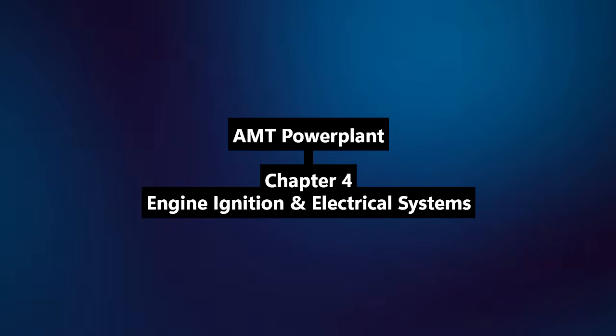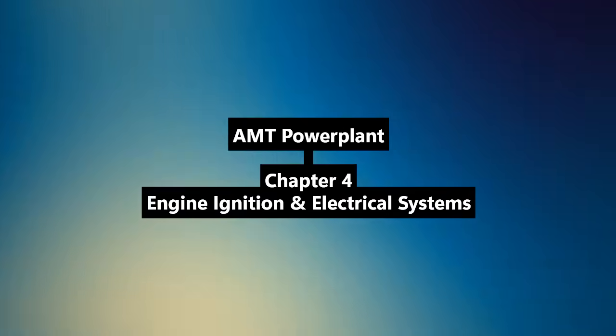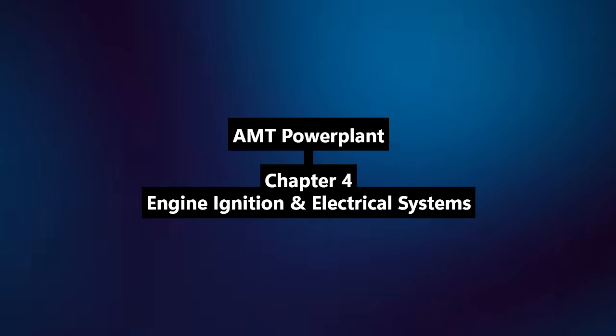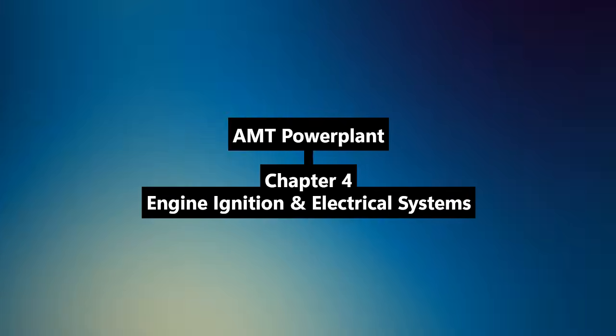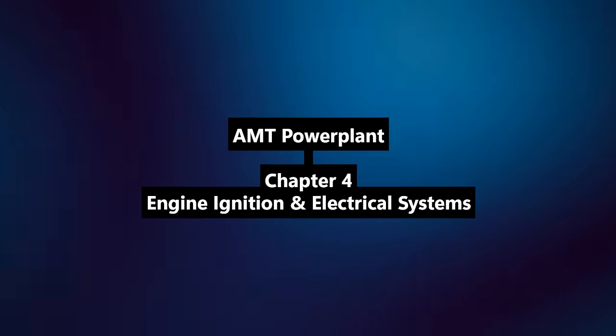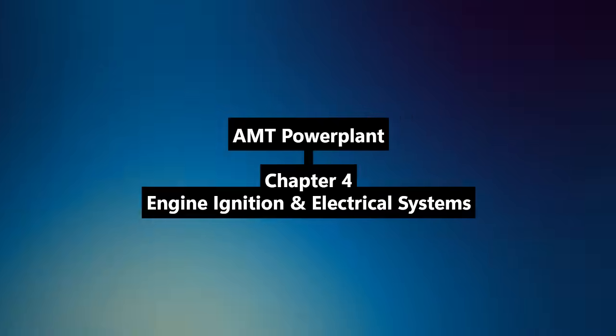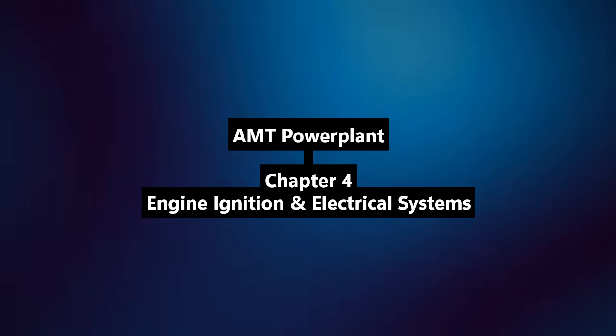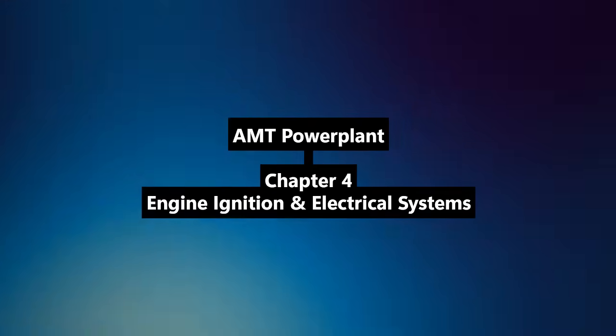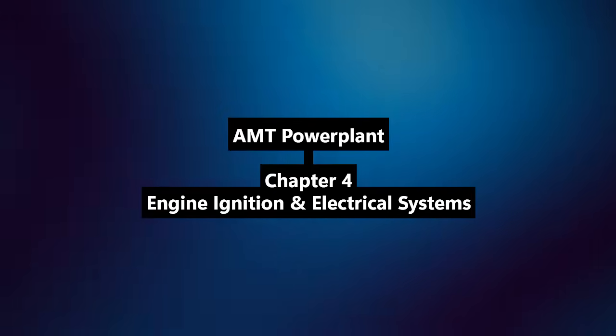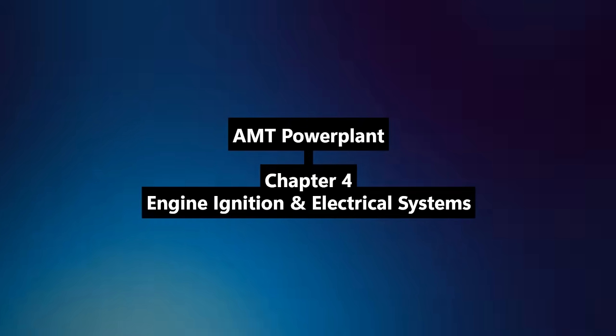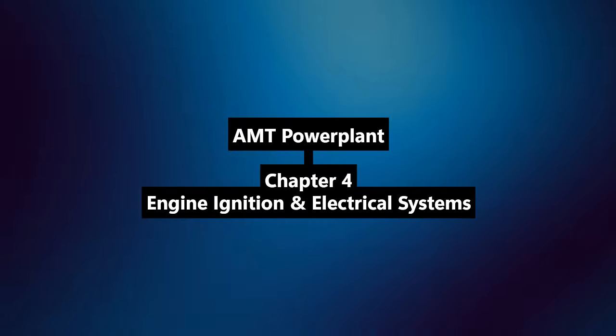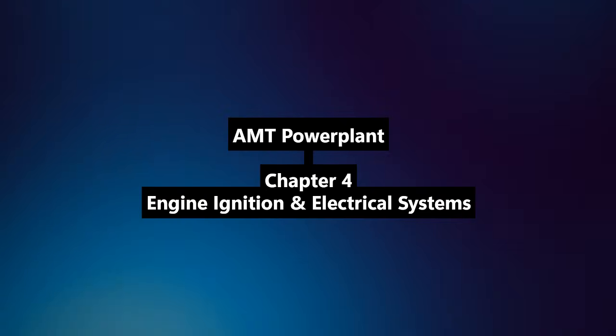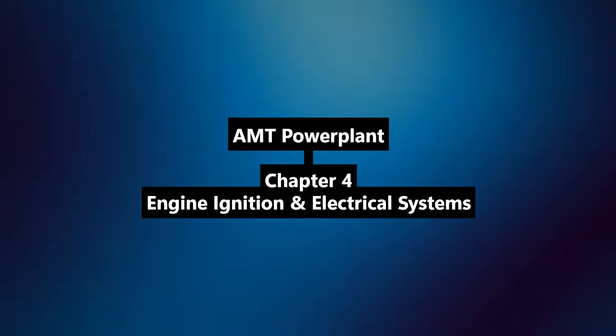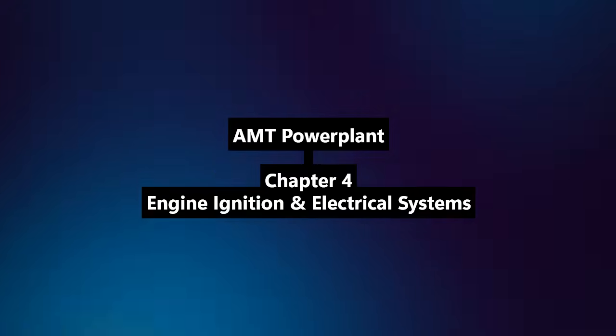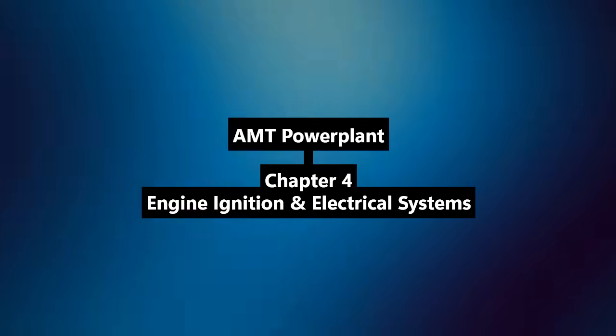and ozone exposure. And how do maintenance technicians go about testing the ignition harness to try and locate these often elusive high-voltage leaks? Harness testing typically involves checking the integrity of the insulation surrounding each individual high-voltage cable within the harness assembly. How do they test the insulation? It's usually done by applying a specific high-voltage charge, often using a specialized harness tester or a megohmmeter, to the conductor at one end, while the outer shielding and the other end are grounded. Then, they measure the amount of current that leaks through the insulation between the center conductor and the grounded shielding.